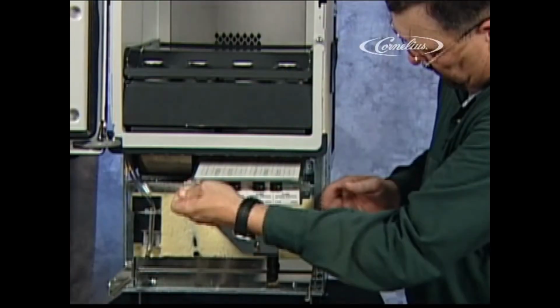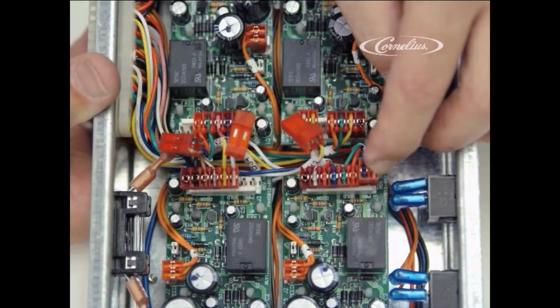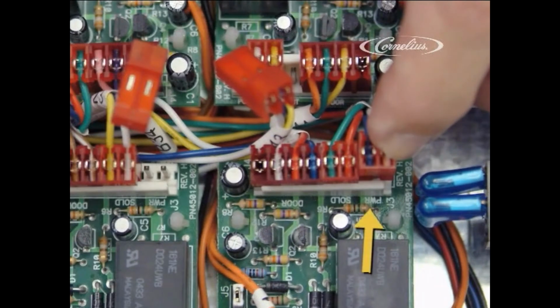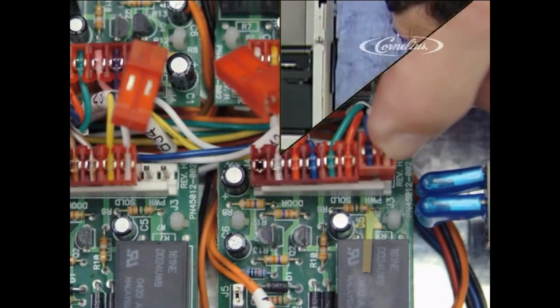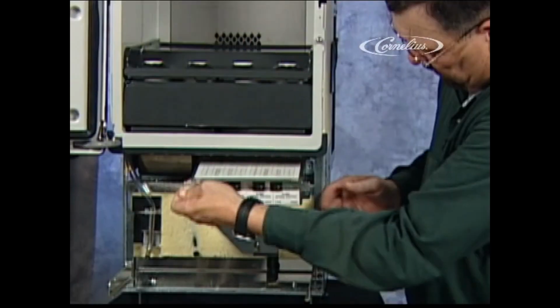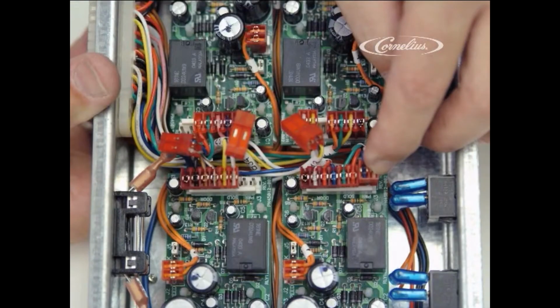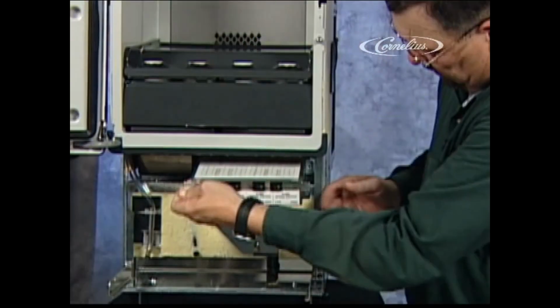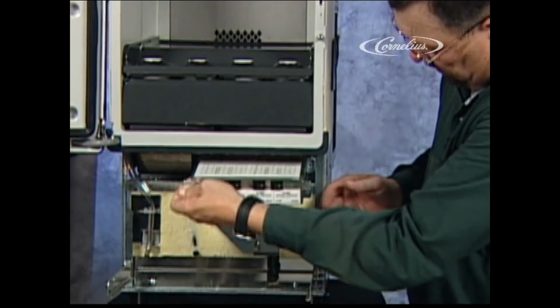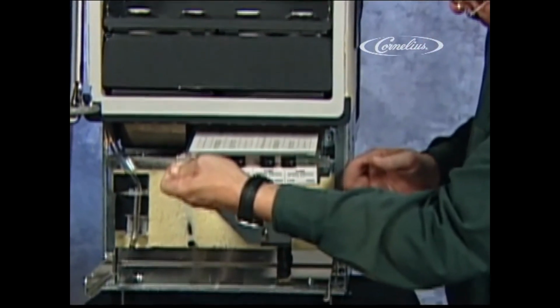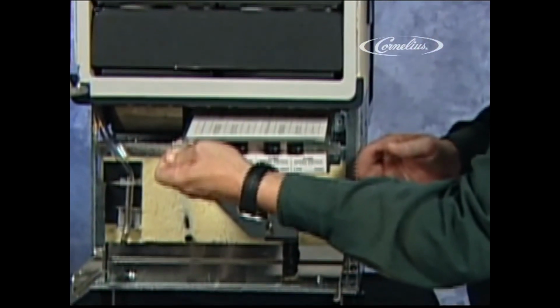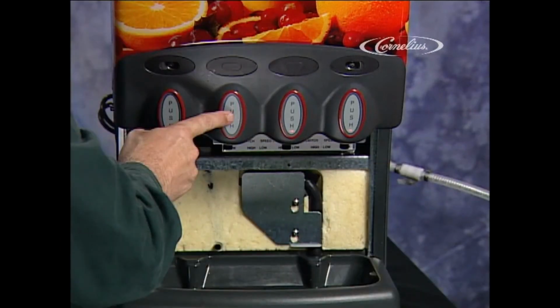Plug the box in to energize. If the fuse remains okay, do this for each input. Repeat this procedure one at a time until all inputs are replaced. This is checking to be sure none of the VRB boards have a dead short causing the fuse to blow immediately. If none of these conditions is present, replace the box in the unit. Activate each pump head one at a time until the fuse blows out again. That will be the board that will need to be changed.